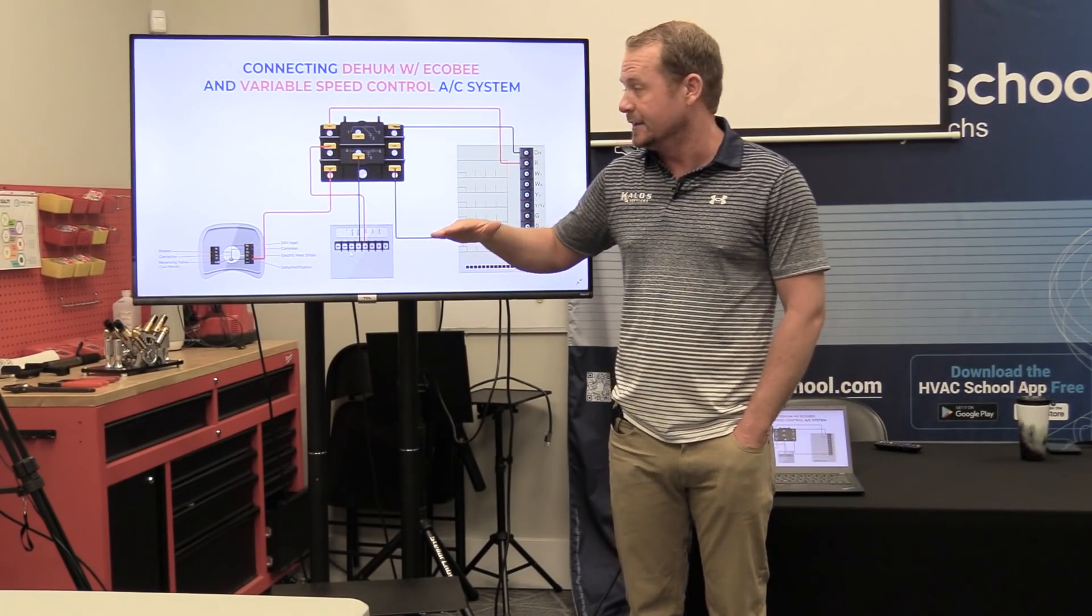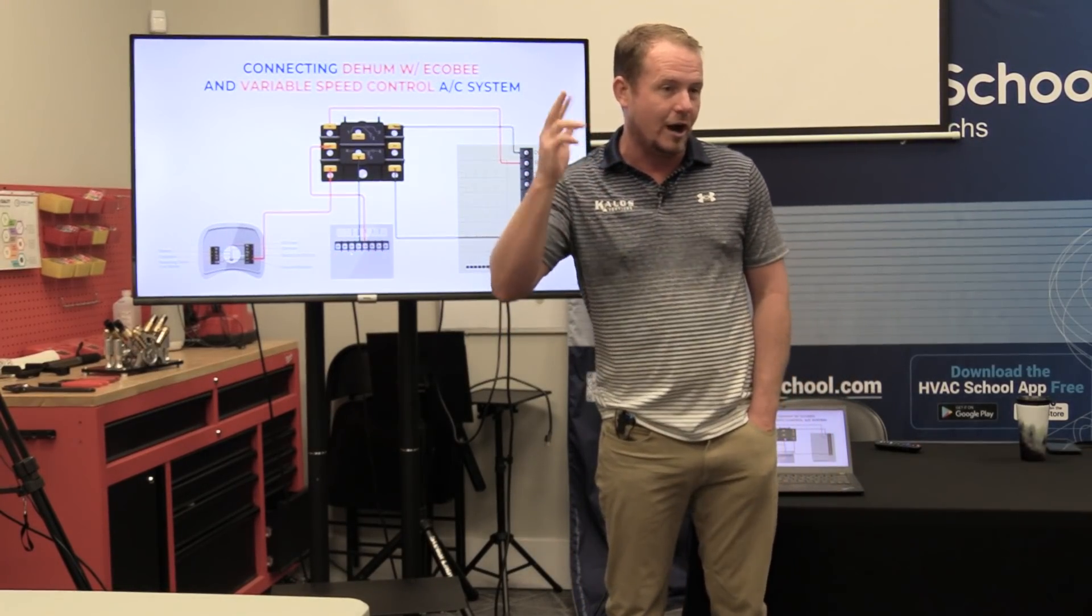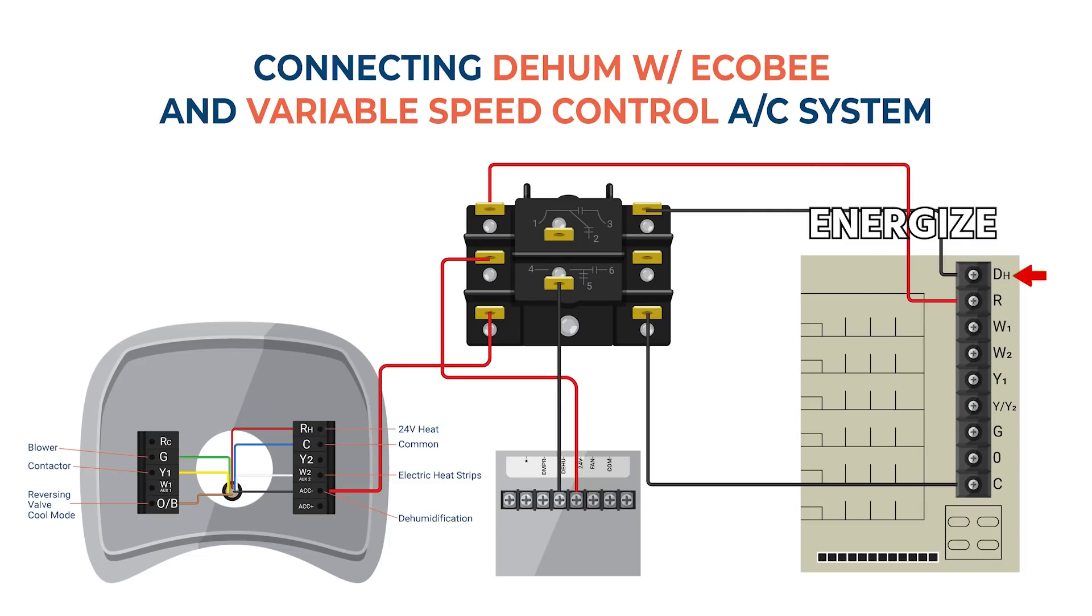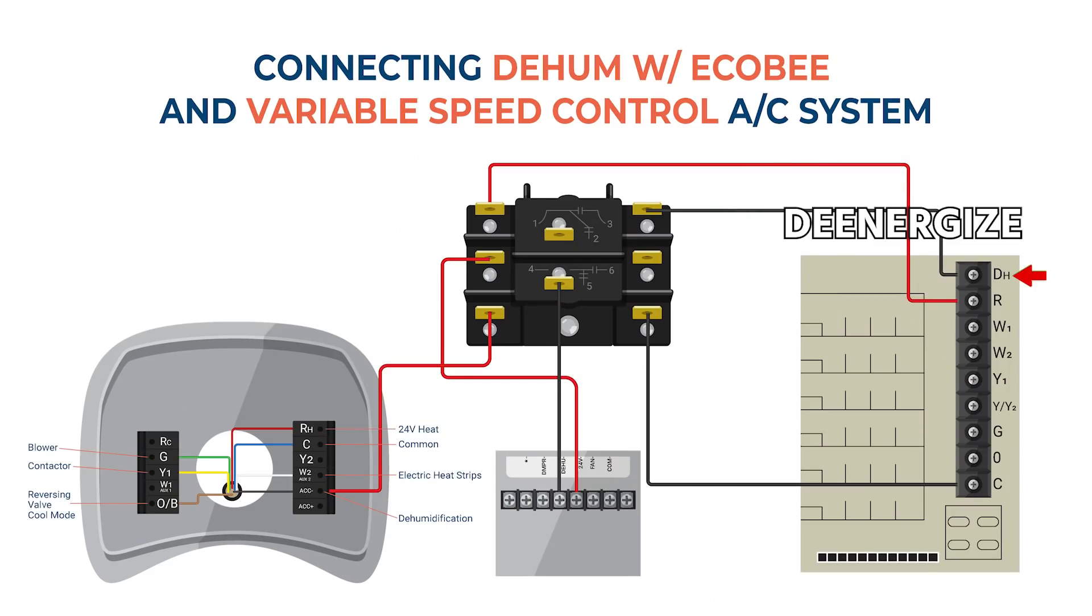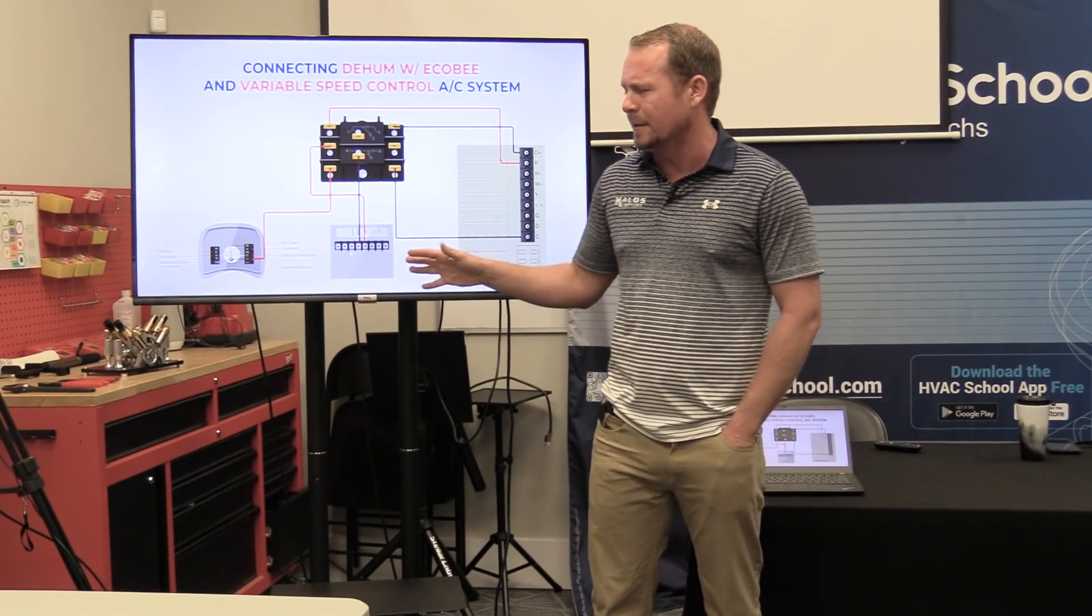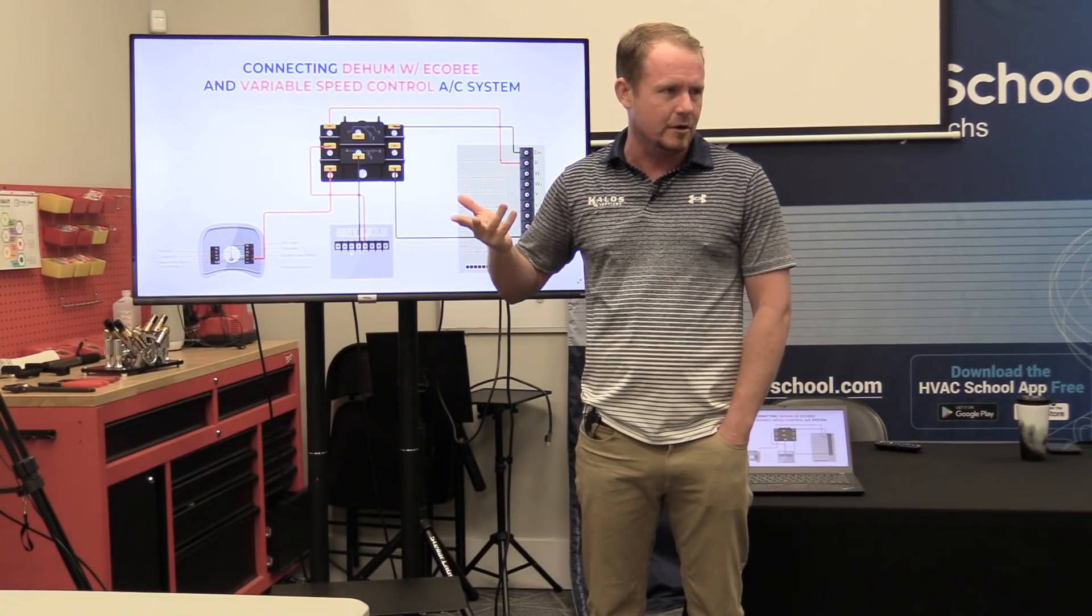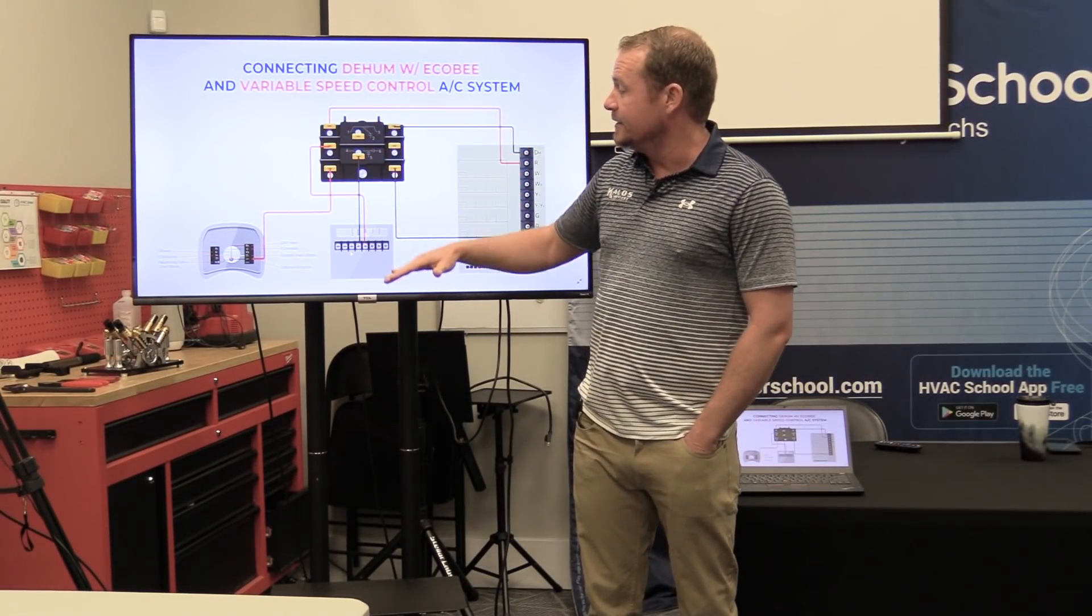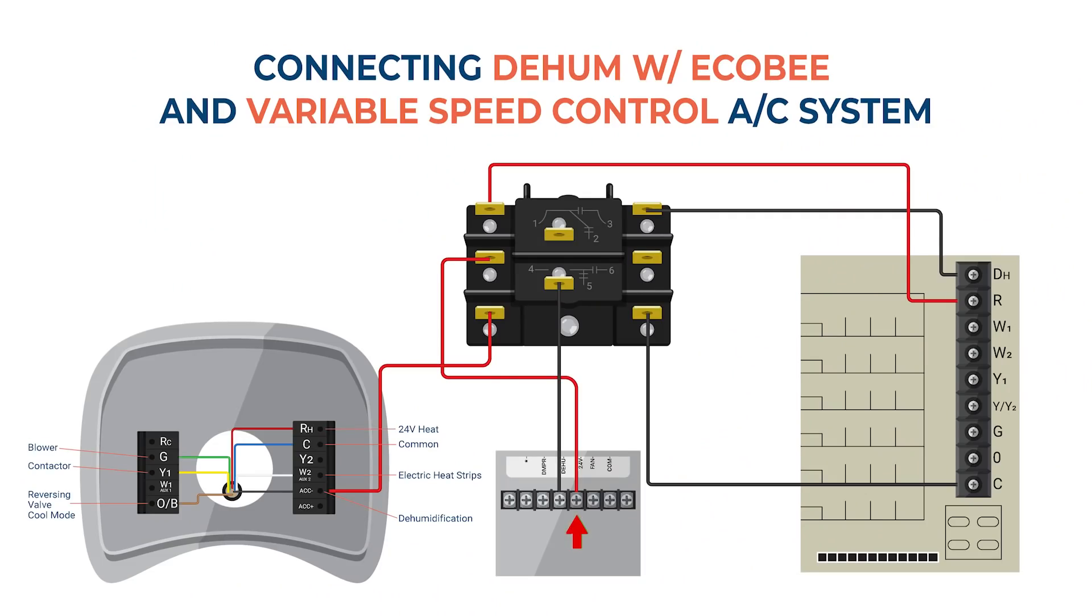Now, where it gets complicated is dehumidify mode for a dehumidifier and dehumidify mode for an air handler are opposite. For a dehumidifier, you energize DH with 24 volts in order to make it run. In an air handler, you de-energize DH in order to make it go into dehumidify mode. So that's why we're doing this. We're also doing it because we have to isolate. Because a lot of people will say, why do you need the relay? Well, we showed why you need it because they're opposite modes. But the other reason we need it is because we need the dry contacts because this has a separate transformer. You can't mix the 24 volts from one transformer with the 24 volts from another transformer.